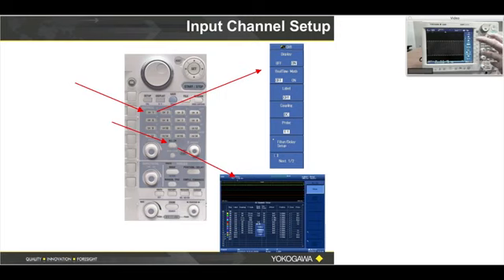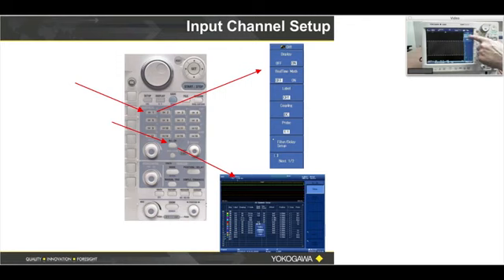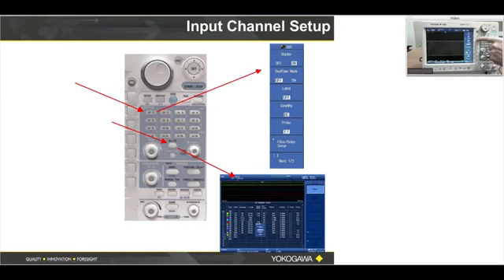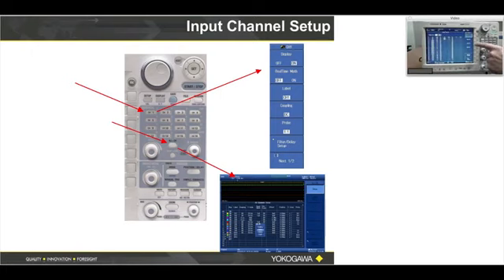If you press the button at the very bottom, soft menu number seven, it says 'next one of two' — this takes you to the second page of soft menus. Button number one here says vertical scale per division. I can choose span — there are two choices. Span can be very friendly and very custom. There's also vertical zoom here, which we can talk about at another time. I have a presentation that will show you how to use vertical zoom to maximize your vertical resolution.